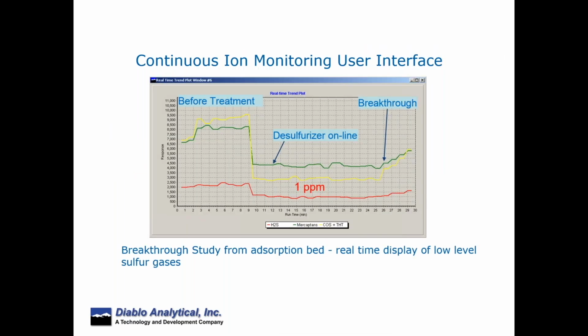Just as an example, obviously we get these run charts, and this shows an example of a breakthrough study from an adsorption bed. You can see that we have a series of sulfur compounds, and around 9 minutes the challenge gas is introduced into an adsorption bed. The objective of this, of course, would be to look for the point at which the bed starts to become saturated. And you can see that around 26 minutes, the signals start to increase as the bed starts to reach saturation. So this is just one of many examples.